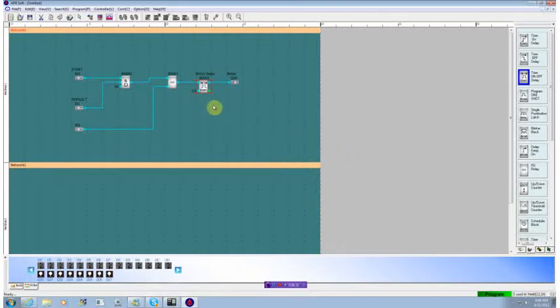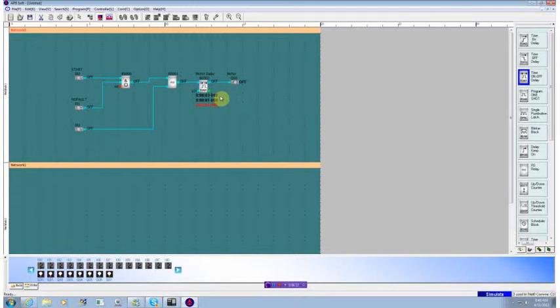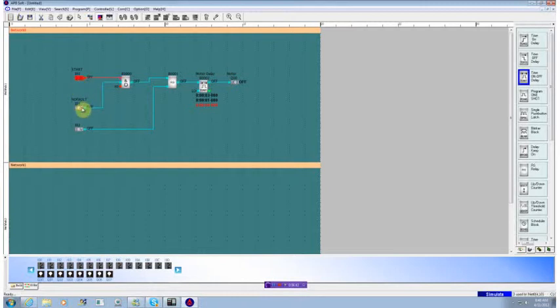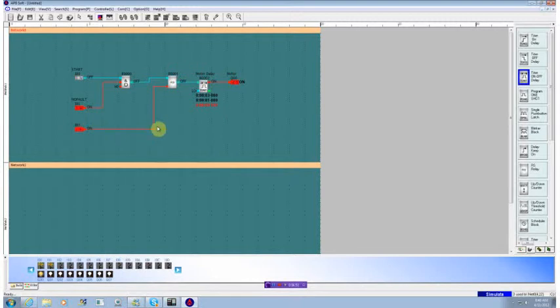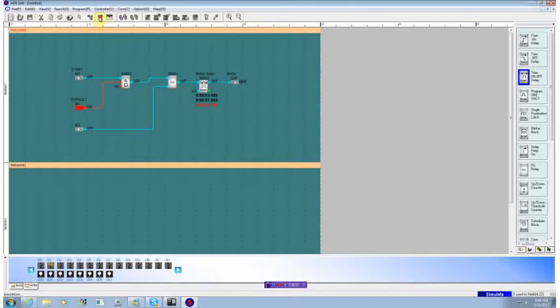Okay, so now if we run our simulator, we see that we've added in our preset on delay or off delay and our running time. So if we hit start, hit the no fault, we see it start running up. When it gets to three seconds, it turns the motor on. If we hit the off, when it gets to one second, it turns the motor off. So we have a simple timed on, timed off motor.